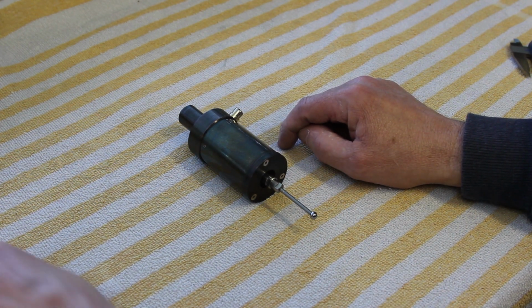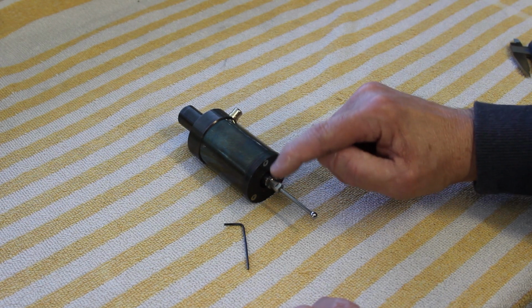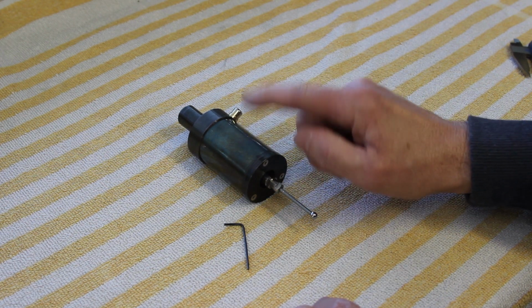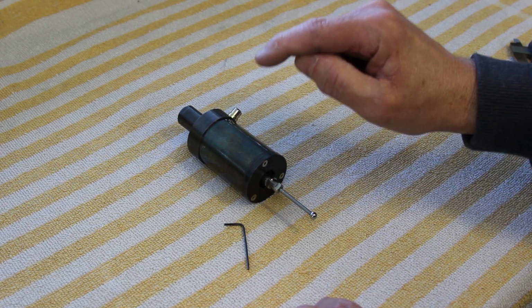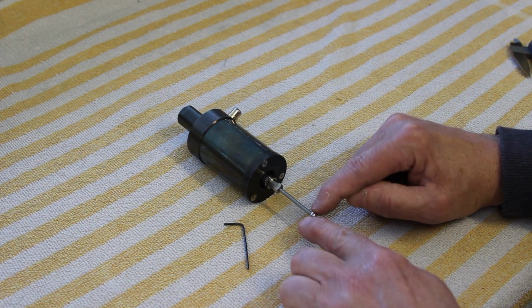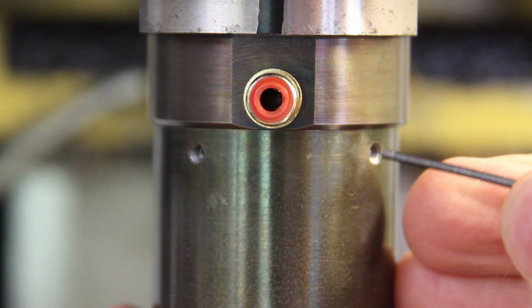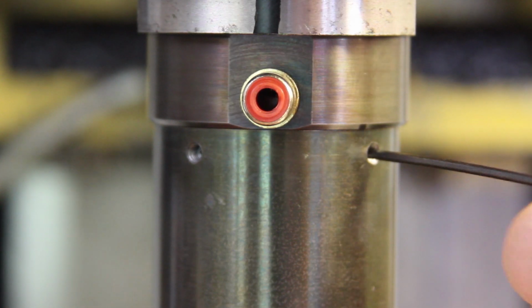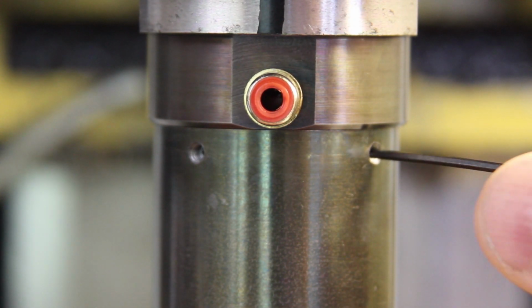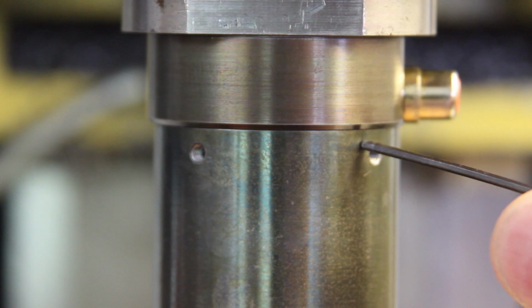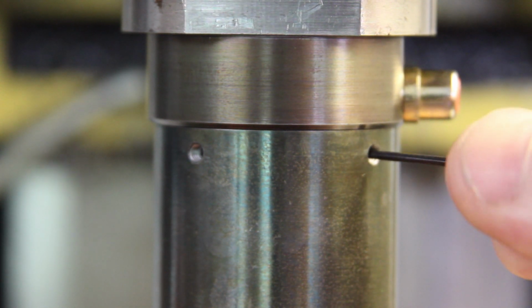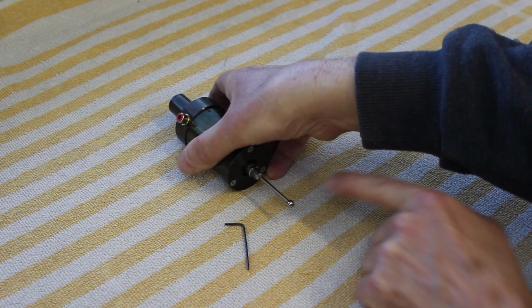So what we're going to do is put this in the spindle of the mill, and we use the mill to do the testing. I'll then dial out the eccentricity in the ball using the 4 grub screws at the top, and then we'll do some testing, and we'll test it for how far it moves before it triggers, and we'll rotate it round 30 degrees and do the same thing.